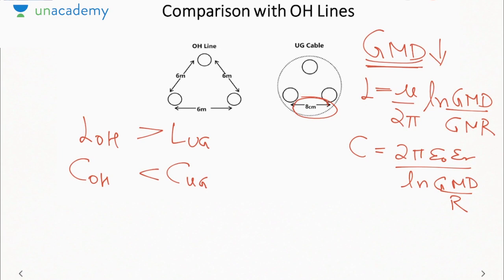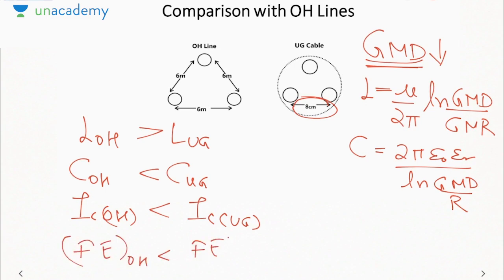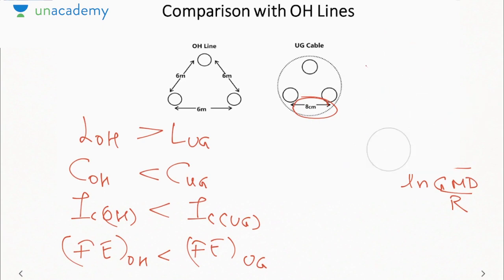Now due to increase in capacitance, what will happen? The line charging current will increase. So IC of overhead line will be less than IC of UG. Due to increase in line charging current, Ferranti effect will increase. So Ferranti effect in overhead line is less than Ferranti effect in UG. So that means we will need more protection or more compensation against Ferranti effect in case of underground cable as compared to overhead line. Now due to reduction in L and increment in C, what happened to the surge impedance?